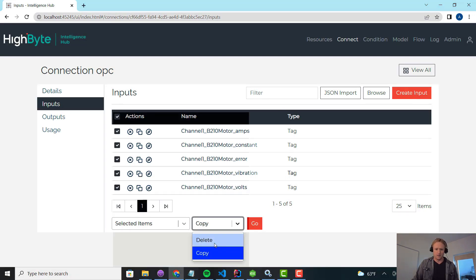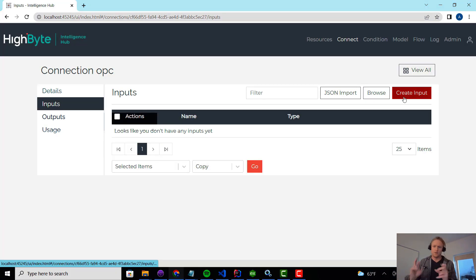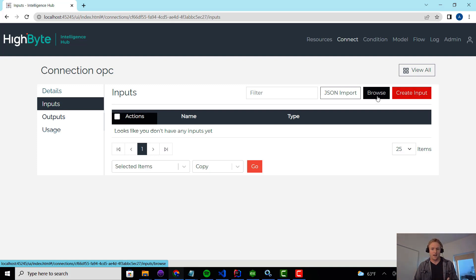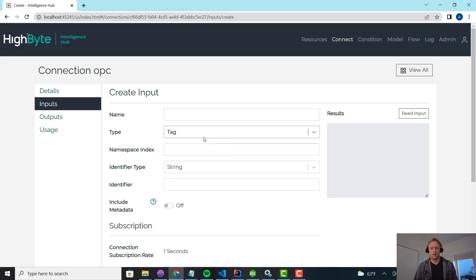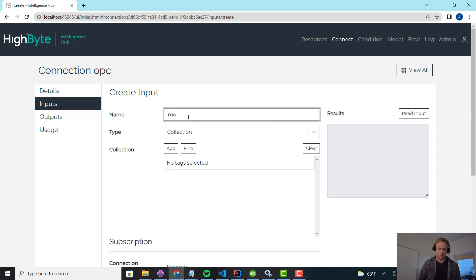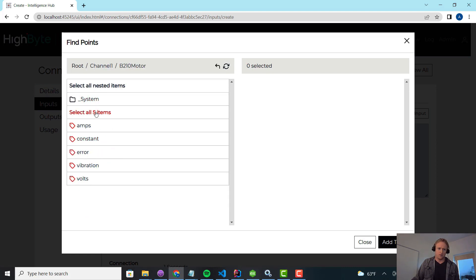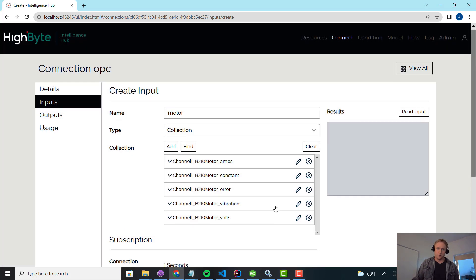Now we have a great answer to that. I'm going to delete this and go back to a blank slate. Instead of creating individual tags as inputs, one of the cool features in 2.4 is the ability to have a collection of tags in OPC UA. I'm going to create an input and switch it from the default tag type to collection, and call it motor. A collection is nothing other than a list of tags to go and read. I'll hit find and grab all the data for the B210 motor, bringing everything in as part of this collection rather than as individual inputs.